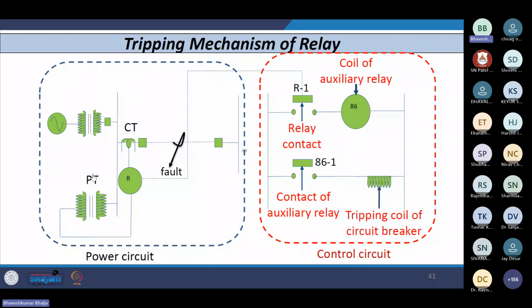Sometimes at distribution level in developed countries they also follow the same mechanism, but here at distribution level and at sub-transmission level, at 66 kV, we are not following that strategy. The utility opens all three poles of the breaker, and then recloses all three poles of the breaker again, right? In developed countries, if there is a fault in R phase, only the R pole of the breaker should open, and then after some time, the reclaim time, it has to be reclosed. This is the strategic difference between developed countries and our country, right?